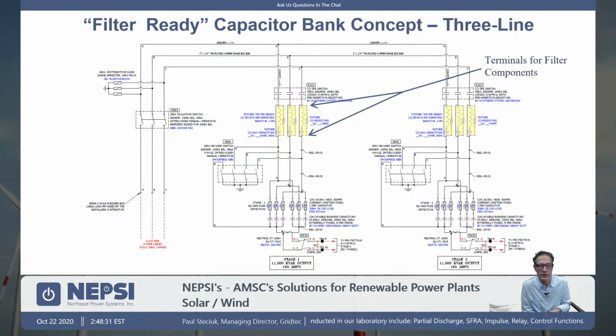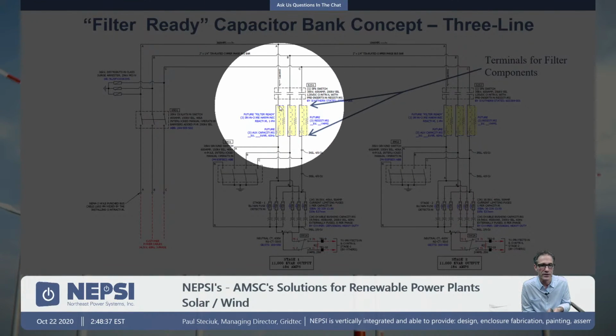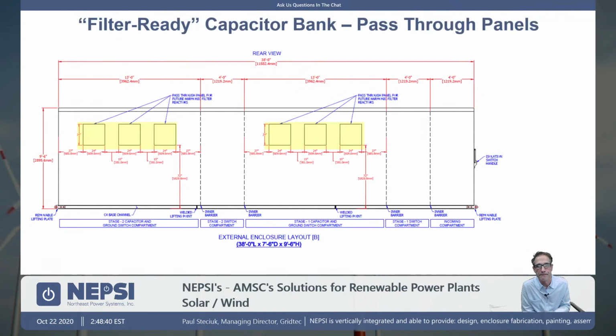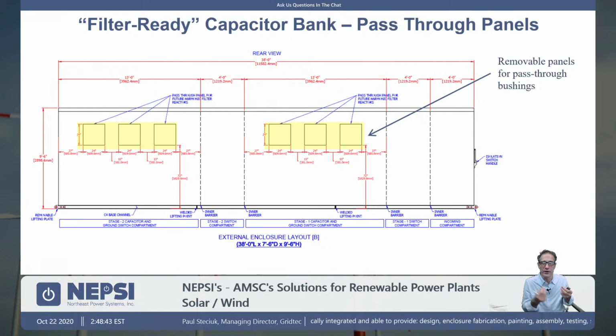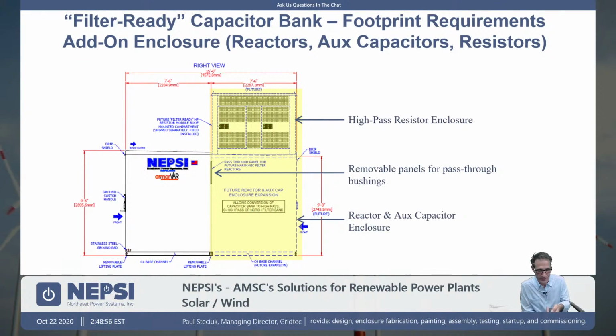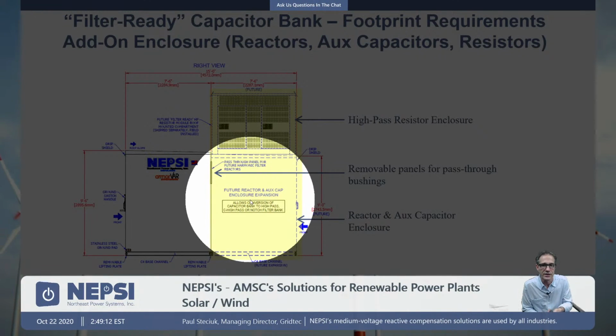This is a 3-line drawing representation of a filter-ready cap bank. Again, the shaded area in yellow you would not get up front; it is something that we could add on at a later date. The enclosure itself has pass-through areas in the back that allow for the passing of medium voltage from a capacitor bank section into a reactor / aux capacitor / resistor compartment. It would have all those, and that's what you see here, in the provisions. The shaded yellow area represents what it takes to convert a cap bank to a harmonic filter bank. You need a resistor cage on top, potentially, and then a reactor and potentially an aux capacitor stage down below. And we would just pass bushings back and forth here.